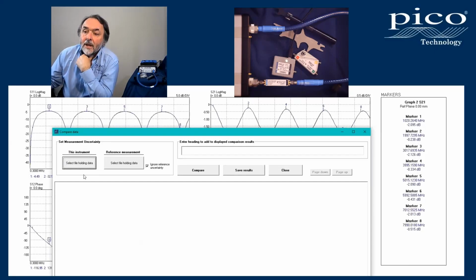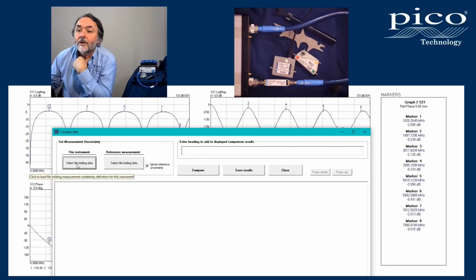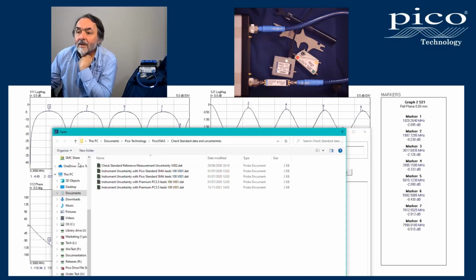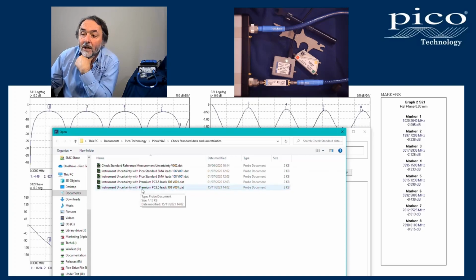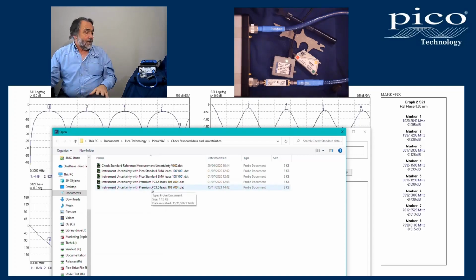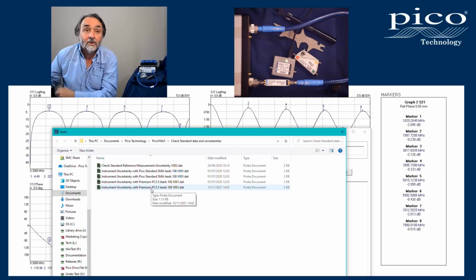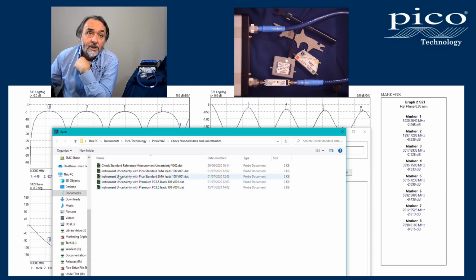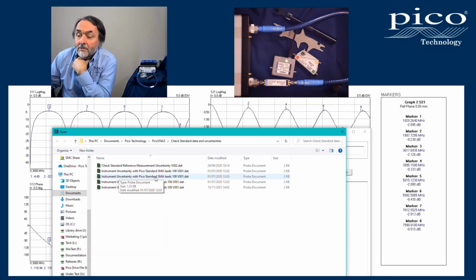With this utility, the compare data utility, we select the file holding the specification or the uncertainties for this instrument, and I'm going to use this instrument uncertainty. It's a PicoVNA 108. I'm using premium calibration leads and adapters here, so PC 3.5. Now I will say the check standard and the eCal module both have SMAs on them. So there is a strong argument that I should be using this uncertainty, because whenever there's an SMA in the system, we should be using a slightly looser specification for the measurement.